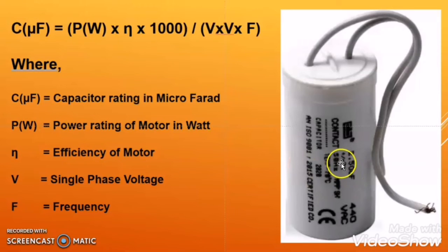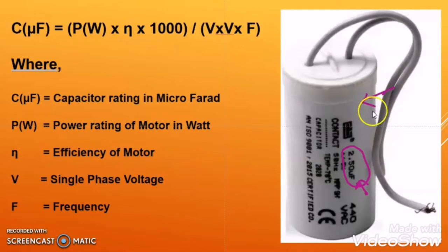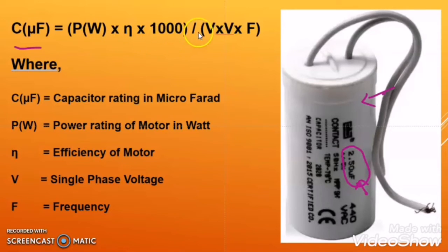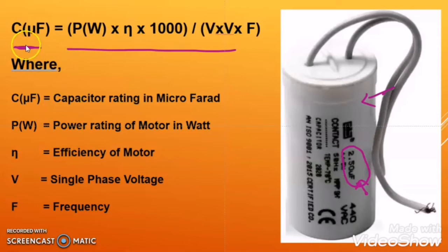You have always seen that on an induction motor there is one rating mentioned — like here it is mentioned as 2.50 microfarad. The formula to calculate the capacitor rating in microfarad is: C (in microfarad) = P (in watts) × efficiency × 1000 ÷ (voltage² × frequency).